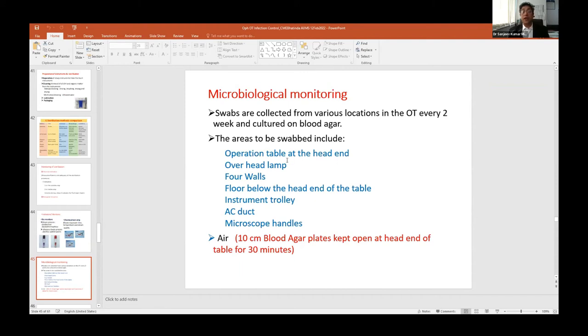The areas to be swabbed include the operation table at the head end, overhead lamp, microscope, microscope handles and objectives, the floor, walls below and at the head end of the table, instrument trolley, AC ducts, and the air. For air sampling, the microbiology people send their technician, and our OT technician supervises all that.